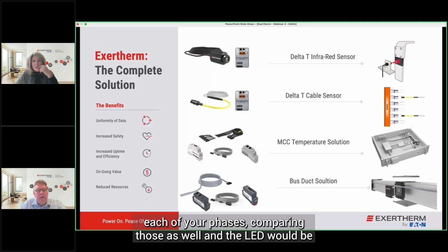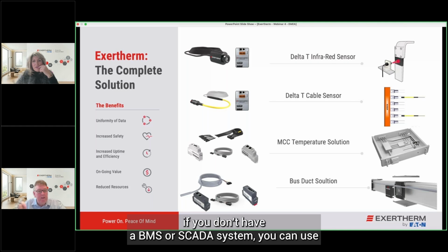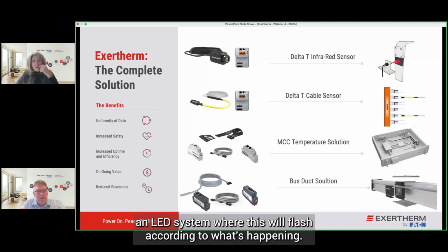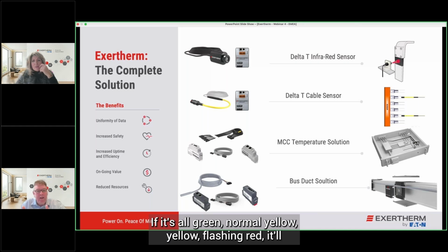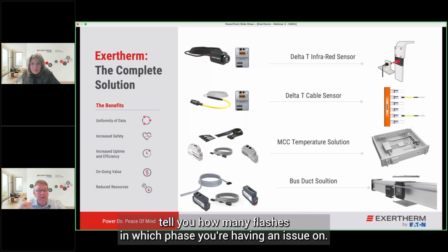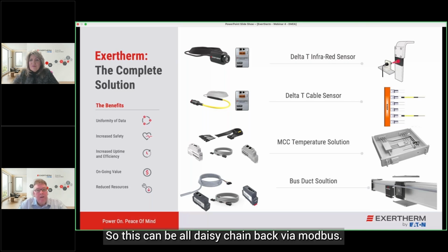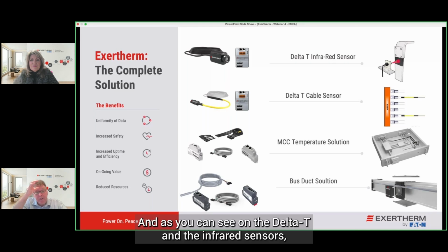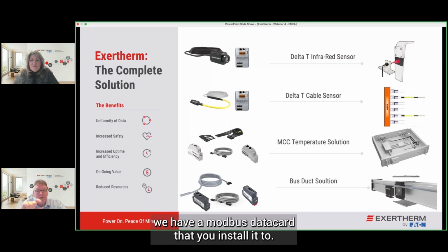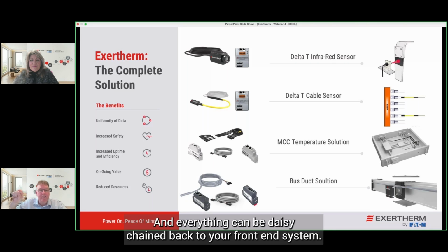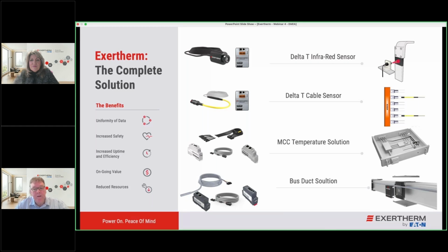And the LED is for if you don't have a BMS or SCADA system; you can use an LED system, which will flash according to what's happening. If it's all green, normal; yellow flashing, red, it'll tell you how many flashes and which phase you're having an issue on. So this can all be daisy chained back via Modbus. And as you can see on the delta T and the infrared sensors, we have a Modbus data card that you install it to, and everything can be daisy chained back to your front end system.